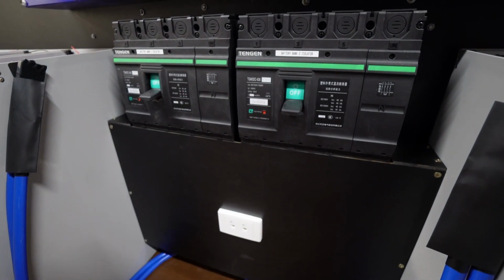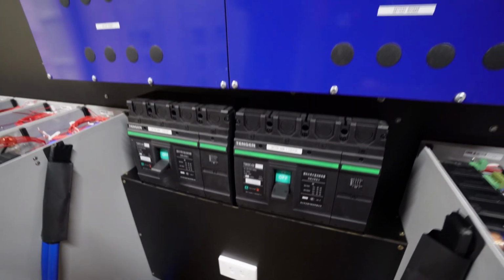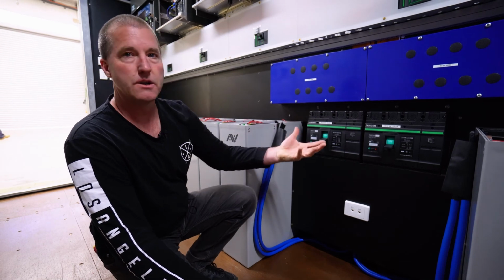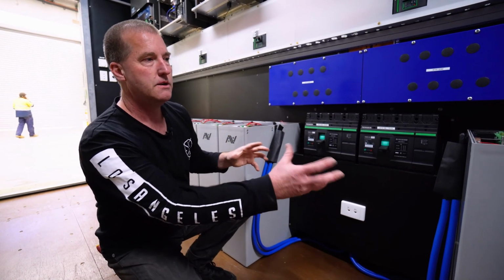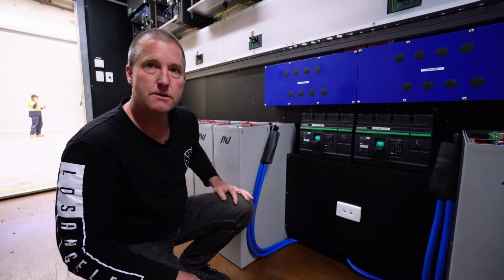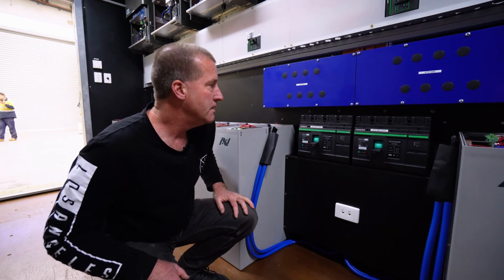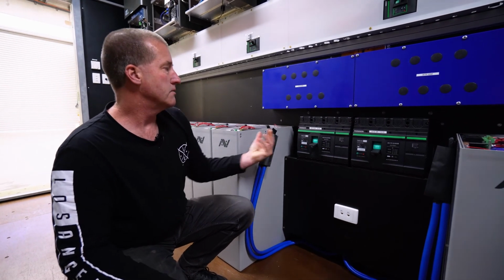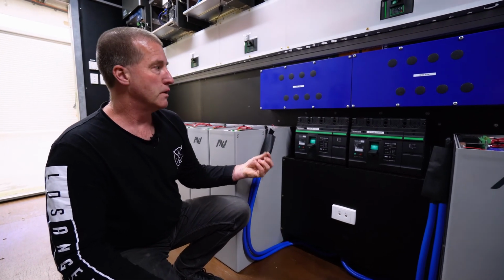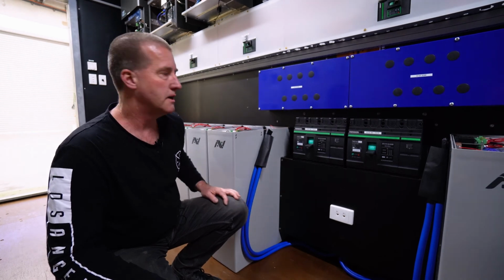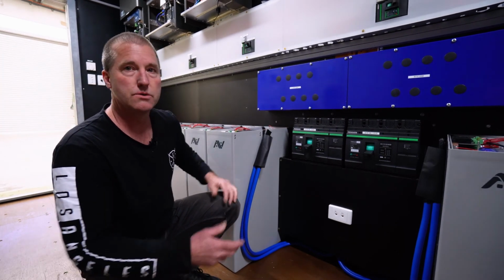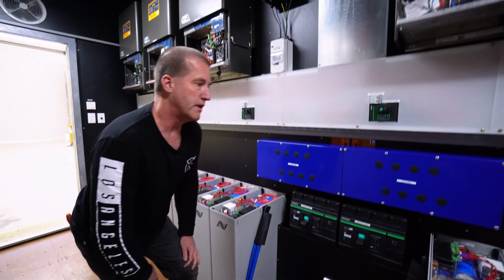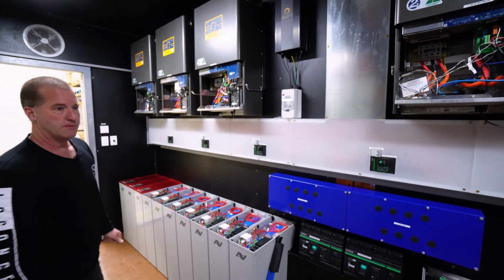There's two strings, and we can remotely trip off one bank of batteries and keep the site alive. So if there's ever a fault anywhere, we detect it, and we can turn off one battery bank until it's remedied. Wow, so you've got remote trip functionality in here. Yeah, it'll trip itself, but if we wanted to, we could trip it remotely as well, and we can see why it tripped and what was the cause of it. Because electronics can fail over time, so we've got to keep an eye on it all.